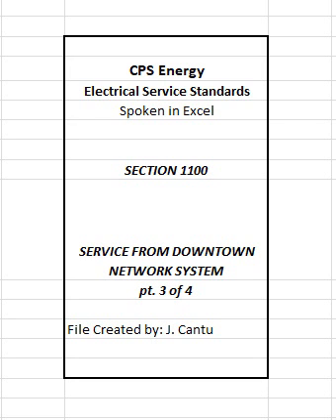1. Be provided with a pentabolt device and sealing and locking means by CPS Energy. 2. Box shall be located immediately before entering the transformer vault or room. 3. Conduits used to penetrate transformer vault or room shall be schedule 40 or 80 PVC with bell ends. 4.